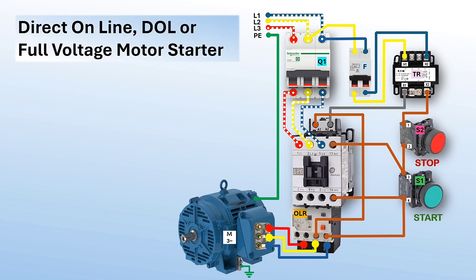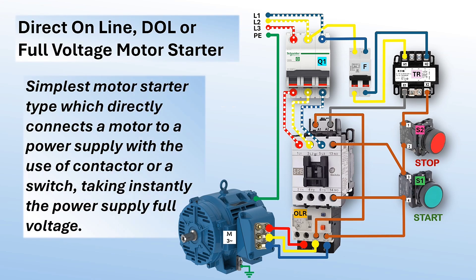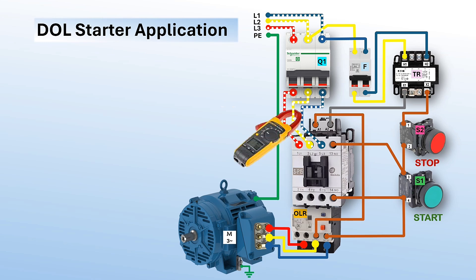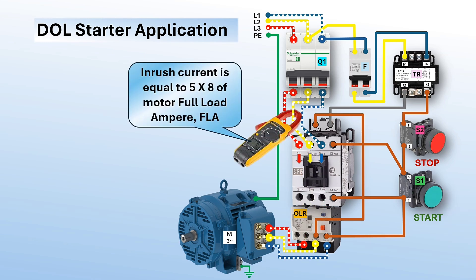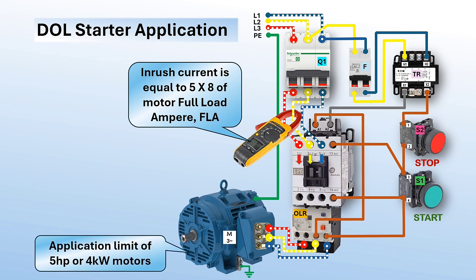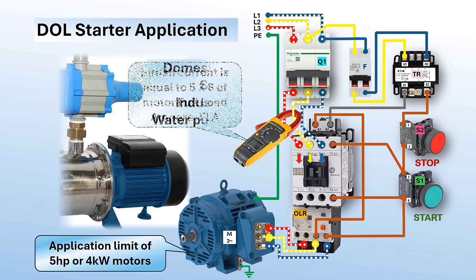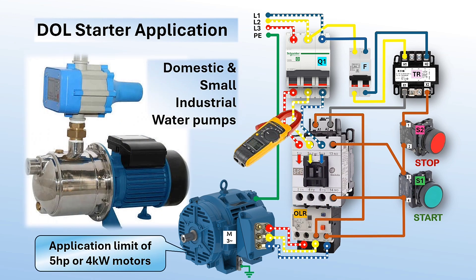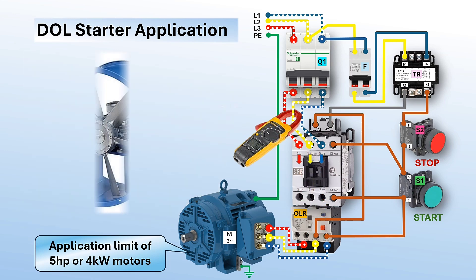What is a direct online motor starter? Considered the most simple motor starter option, direct online or DOL is a full voltage motor starter through a switch or a contactor. This starter instantly connects a motor to the power supply. This full voltage connection can cause the motor to draw an inrush current of five to eight times its normal operating current, making DOL starters generally applicable with low-rated motors under five horsepower or four kilowatts. This type of starter is commonly used to start small domestic water pumps, conveyor belts, fans, and compressors.